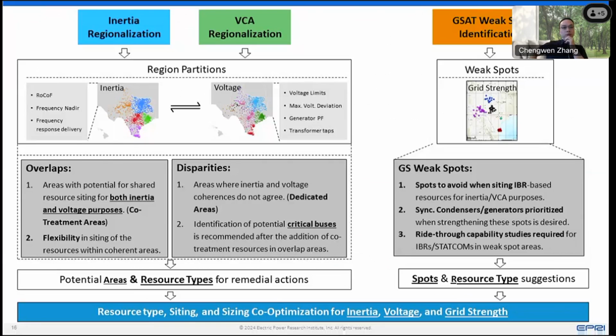The idea is to first bring the inertia and voltage control tool together, the regionalization coming out of the frequency and voltage aspects. If you have overlaps, there are opportunities for co-treatment, allocating a resource to attend to both inertia and voltage purposes. But if there are disparities, we can identify critical buses in those dedicated areas to solve critical issues. Grid strength tends to give us smaller spots where there is very low grid strength or short circuit capability. In those regions, we want to avoid siting more IBRs and instead prioritize synchronous condensers and generators. If you must put IBRs or StatCom in those areas, ride-through capabilities are recommended to ensure safe operations.